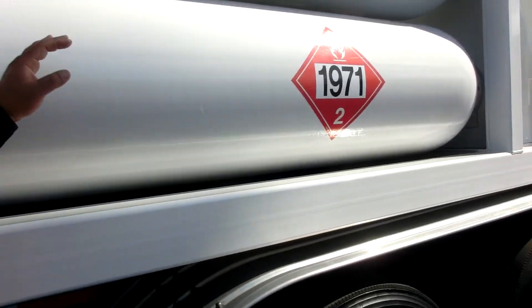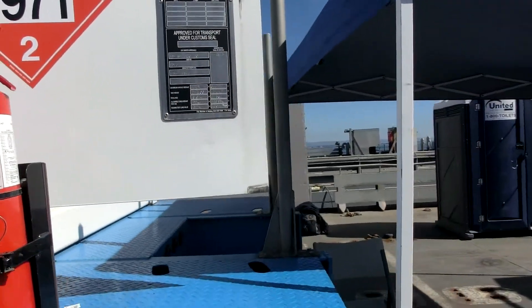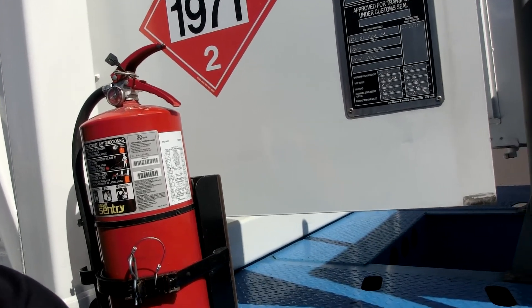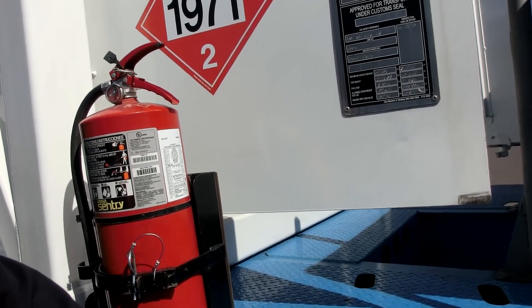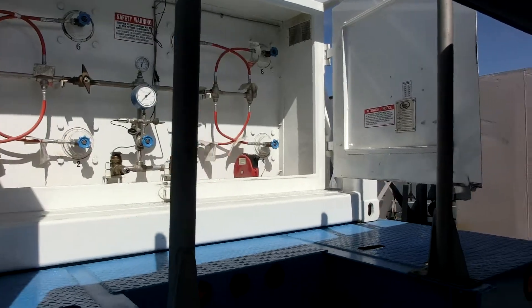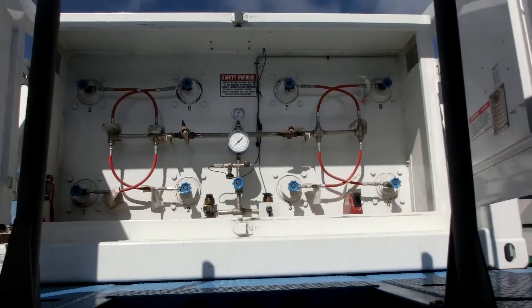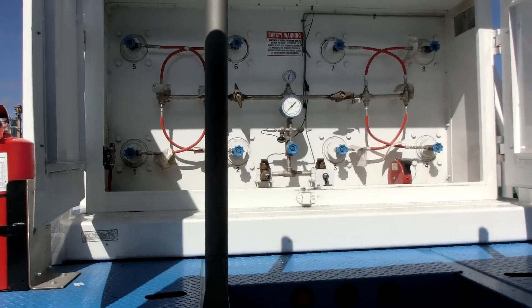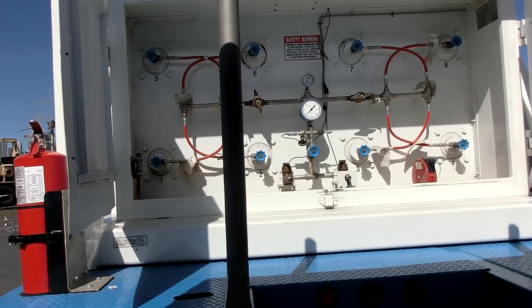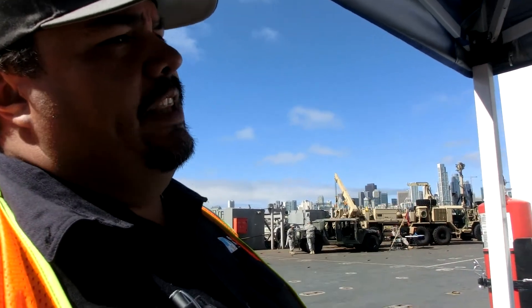What we need to do is take this gas and put it into our pipeline system to maintain customers. So we need to take that 2400 PSI and cut it down to a pressure before we inject it into our pipeline. These eight bottles are manifolded together, so once on site you open all the valves and they equalize to basically one single bottle, giving us the full capacity of the trailer to offload and inject into the pipeline system.